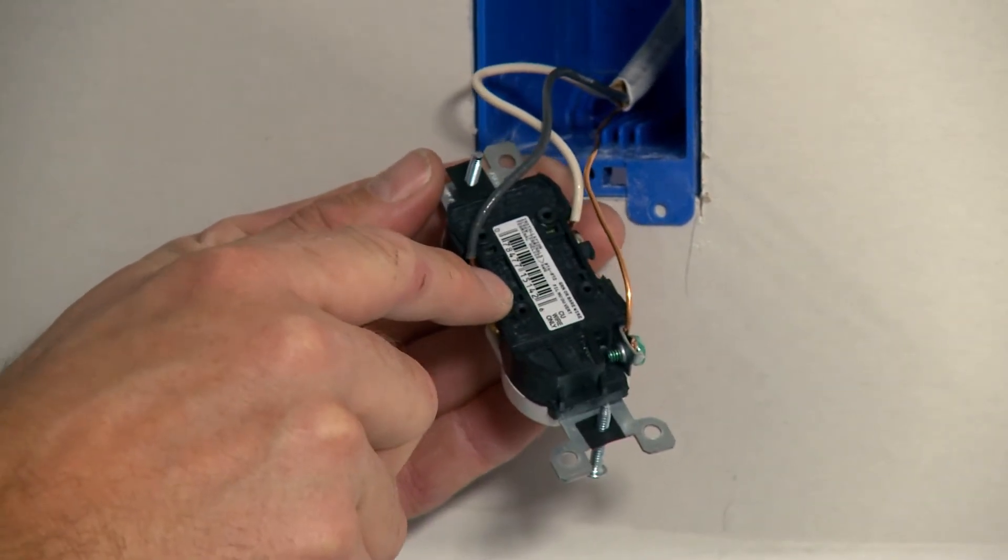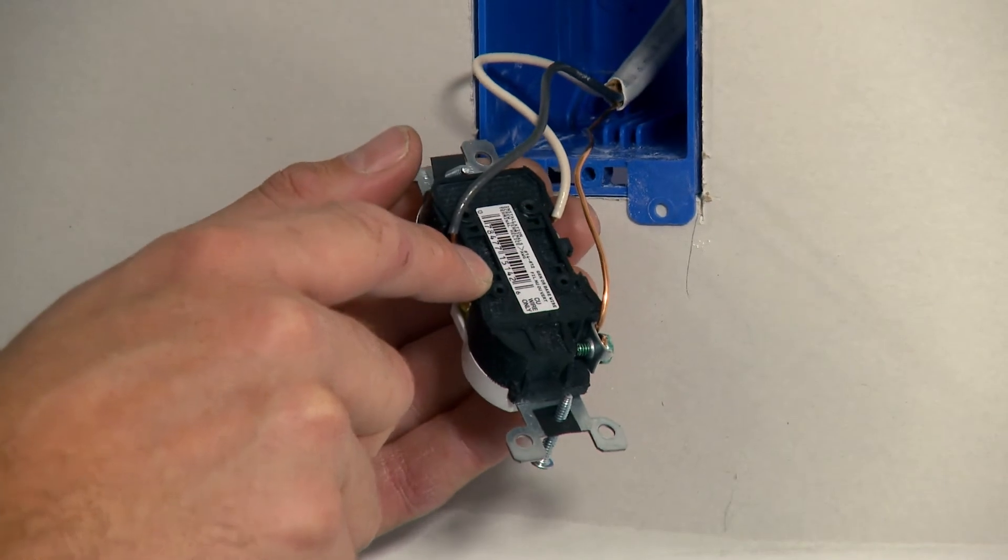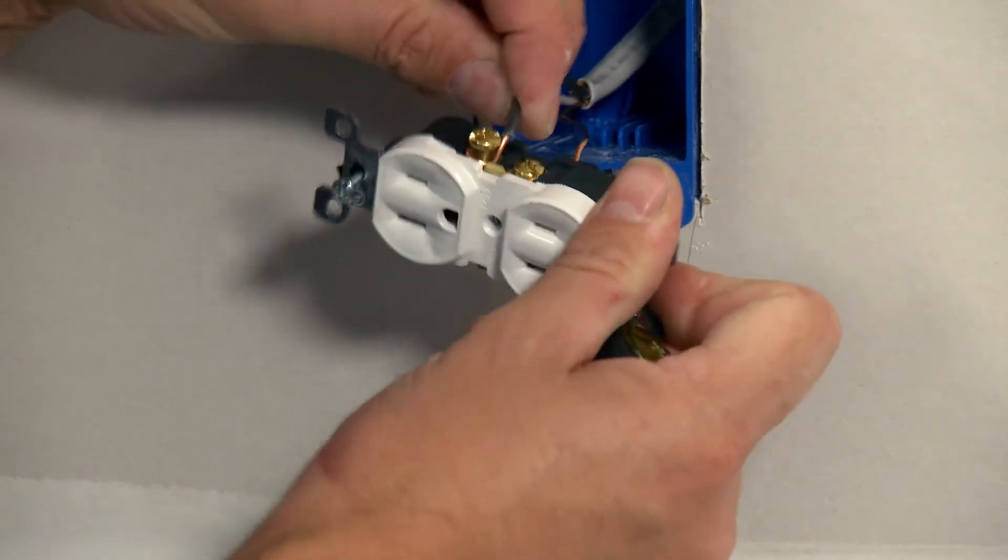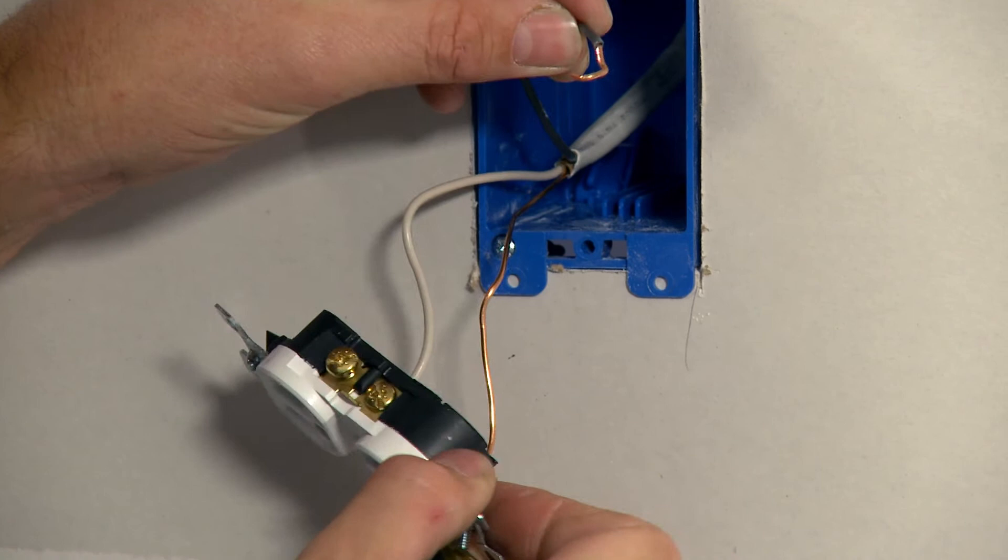If they are pushed in these holes back here, you will need a small bladed screwdriver to insert right there. That takes the pressure off the clamp and allows you to pull the wire directly out. If they're wrapped around the screw like this, sometimes it'll take a little work, but for the most part, they should come right off like that.